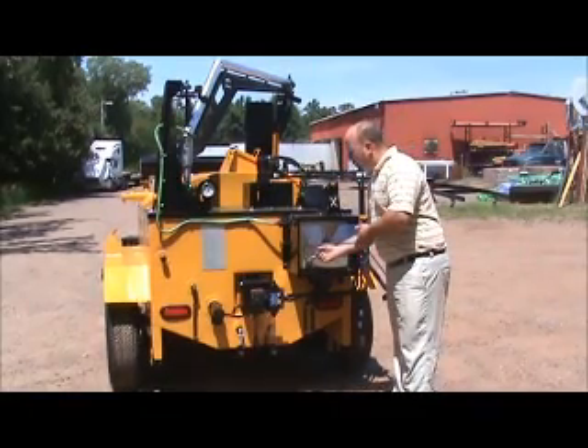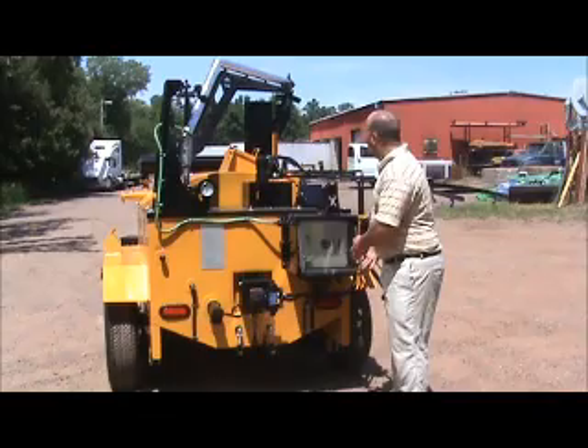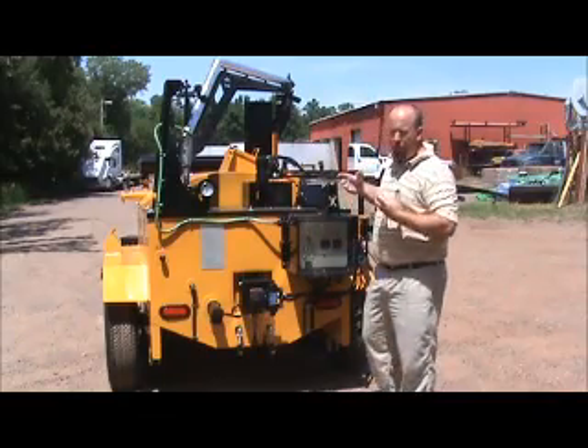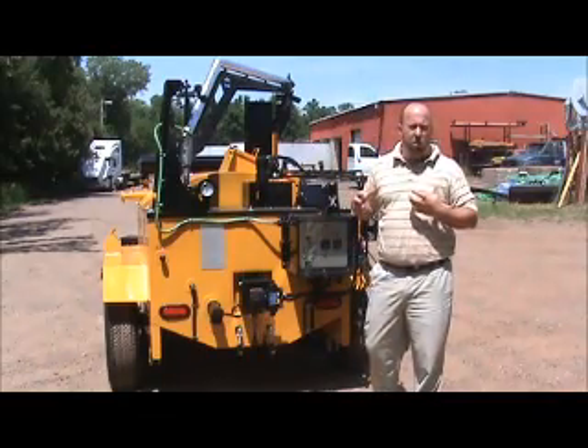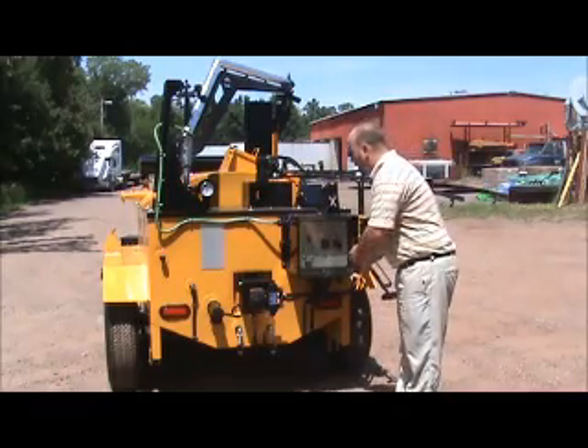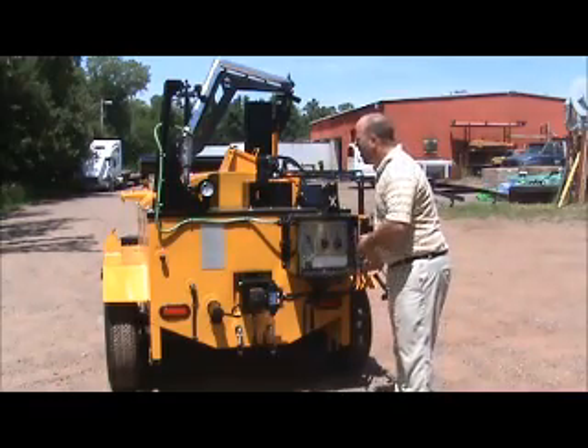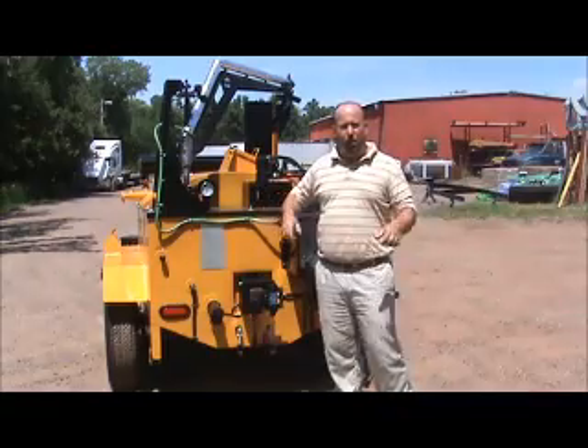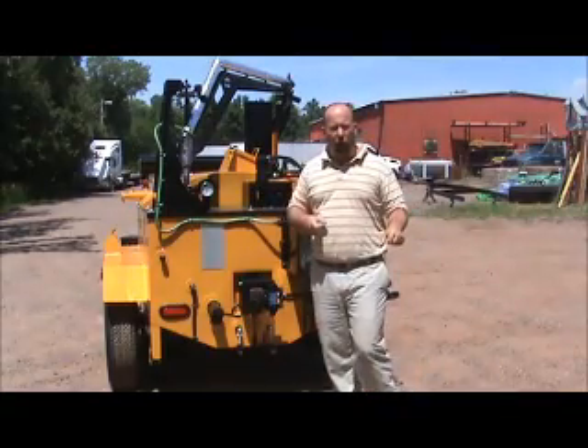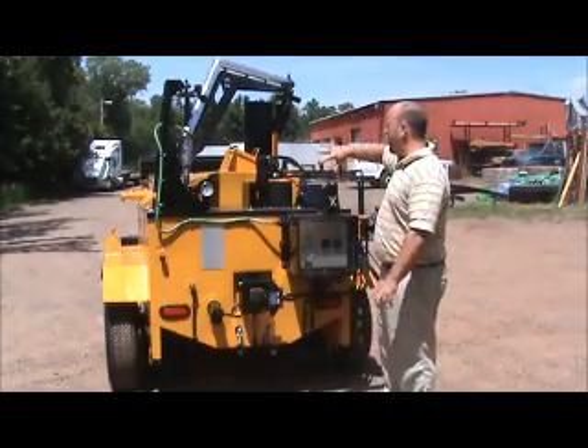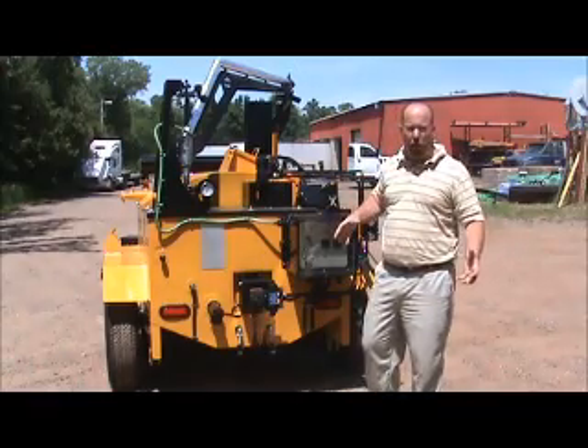I always tell the guys that when we unhang the wand and get ready to start thawing the wand out and pumping product through there, as soon as we do that, we're going to turn the wand control switch on. That's going to stop the pump. The only way the pump is going to turn now is if we pull the trigger. Without that, you can actually have a live wand with no ability to shut it off.